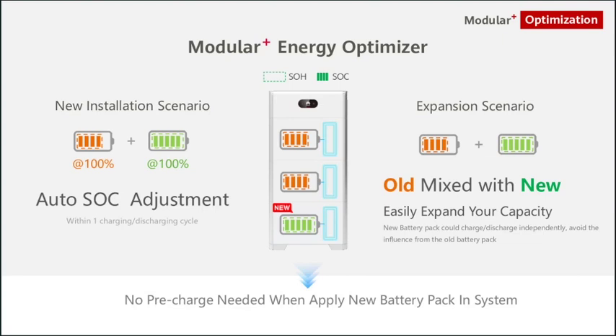With our battery management system on the pack, we can reduce the installation time because we do not need any pre-charge or discharge procedure before adding this new pack into the system. We just click it into our wiring inside the existing system, and everything else is done by our battery management. This reduces installation time since we don't need a pre-charge procedure, and due to the independent management of each pack, we enable the full Luna battery to always provide the maximum capacity available. So there's no negative impact from old to new packs, over the entire lifetime of the battery.